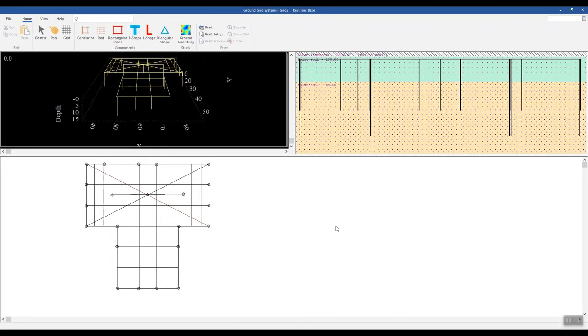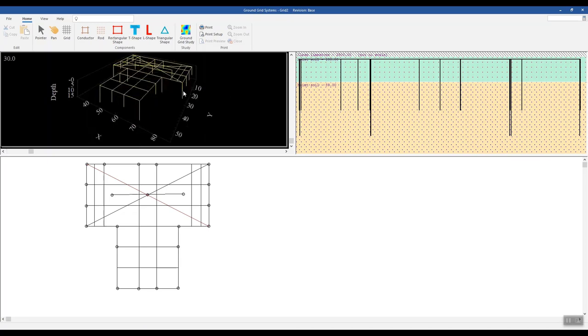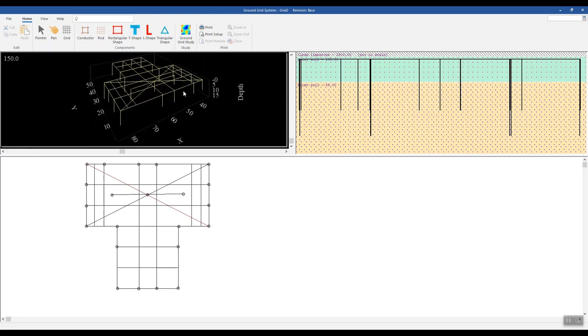Ground grid analysis is used to determine the maximum allowable current for specified conductors and also the step and touch potentials. Here we see the grid in a 3D plane. We can rotate it along the x-axis. Below that is the same grid, but we're viewing it from an aerial perspective.